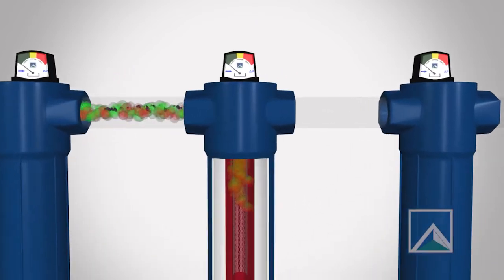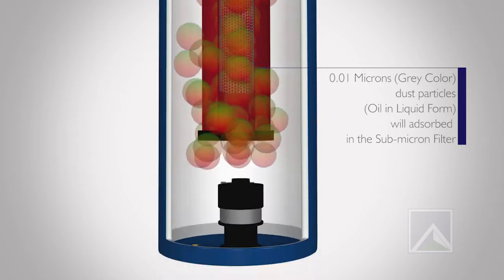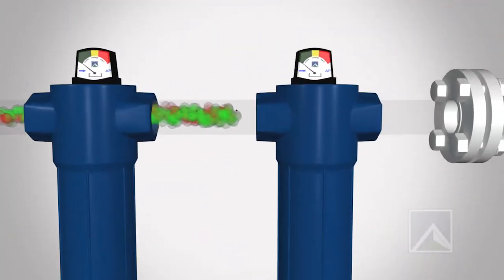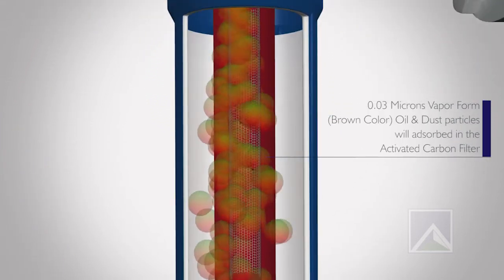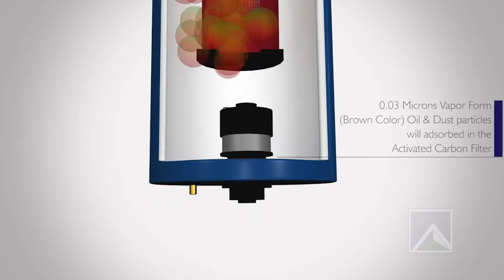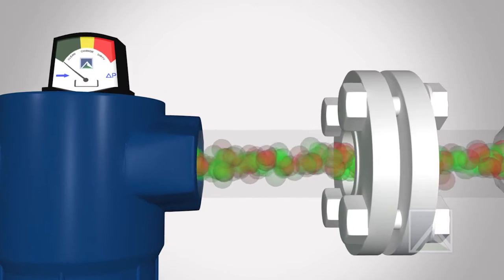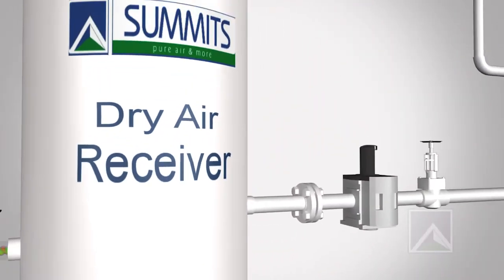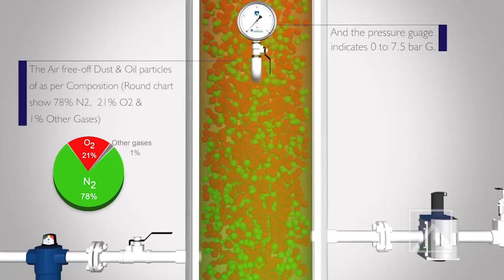The Sub Micron Filter removes 0.01 micron sized particles in liquid form. The Activated Carbon Filter absorbs 0.03 micron sized particles and oil in vapour form. The dry air tank receives moisture-free air and stores it up to 7.5 bar G.